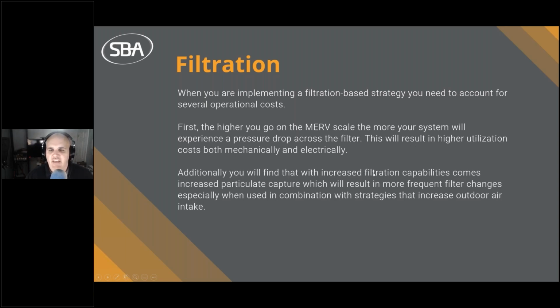Additionally, you will find that increased filtration capabilities come with, guess what? Increased particulate capture. Now, this is going to result in more frequent filter changes, especially when used in combination with strategies that increase outdoor air intake. Because if you aren't cognizant of AQI, the outdoor air quality, and you're bringing in more air, then you're going to find yourself having a lot of particulates hit your filters, which is going to increase filter changes.